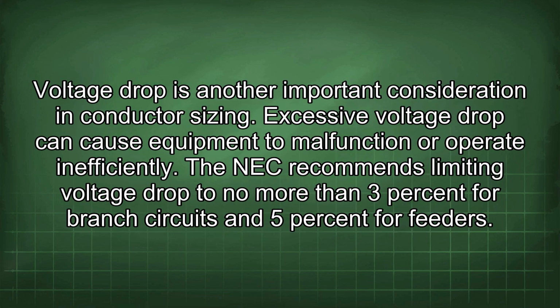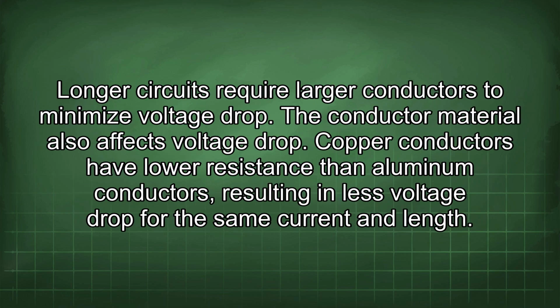Voltage drop is another important consideration in conductor sizing. Excessive voltage drop can cause equipment to malfunction or operate inefficiently. The NEC recommends limiting voltage drop to no more than 3% for branch circuits and 5% for feeders. Longer circuits require larger conductors to minimize voltage drop. The conductor material also affects voltage drop. Copper conductors have lower resistance than aluminum conductors, resulting in less voltage drop for the same current and length.